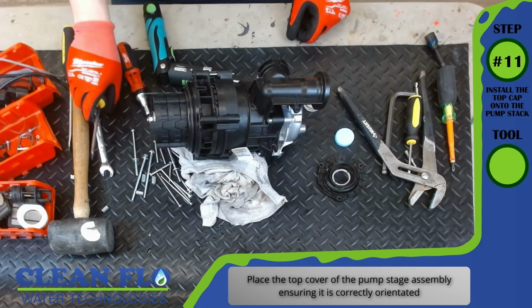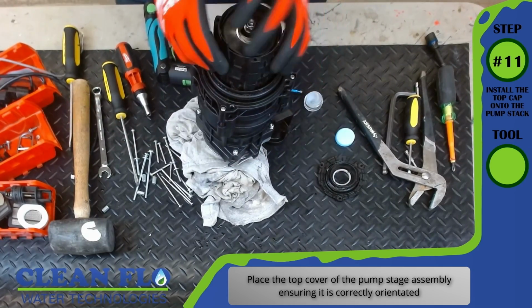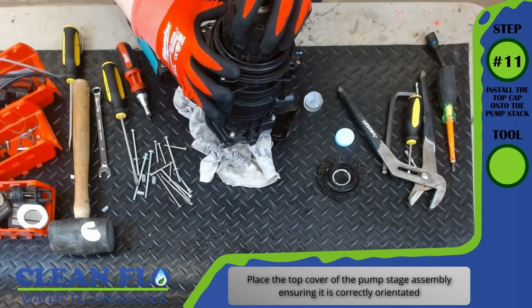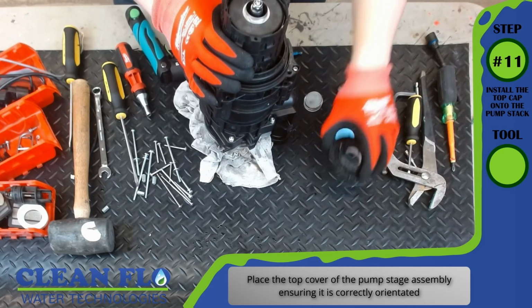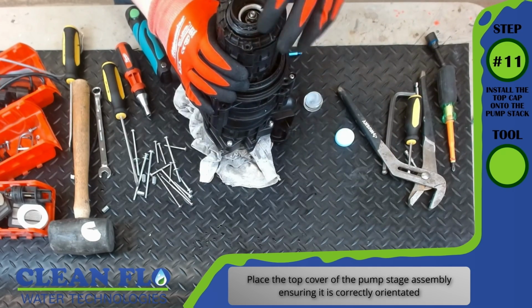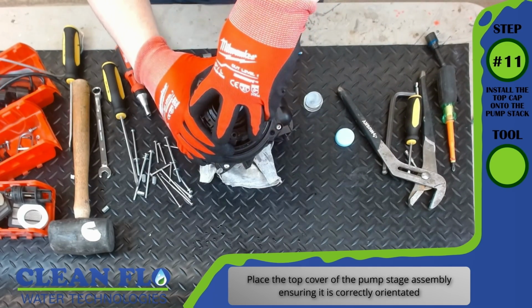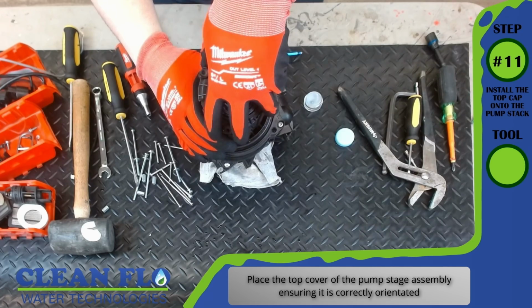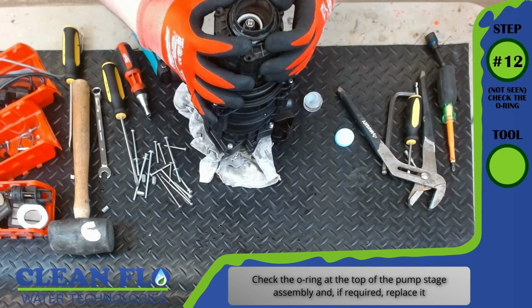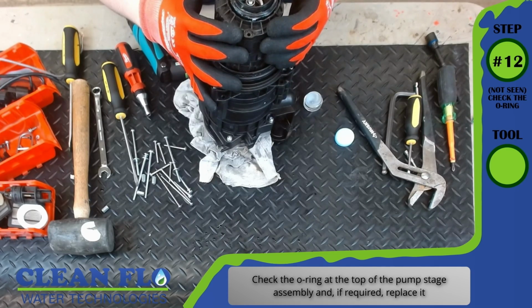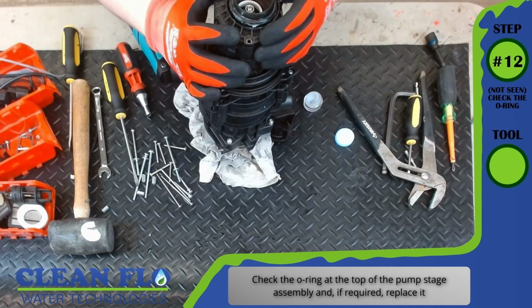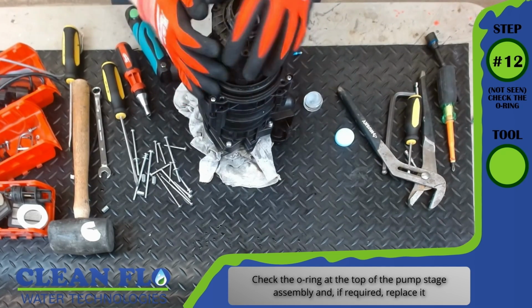Step number 11, install the top cap onto the pump stack. Place the top cover of the pump stage assembly, ensuring it is correctly orientated. Step number 12, not seen. Check the O-ring at the top of the pump stage assembly, and if required, replace it.